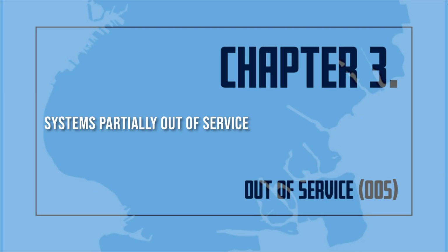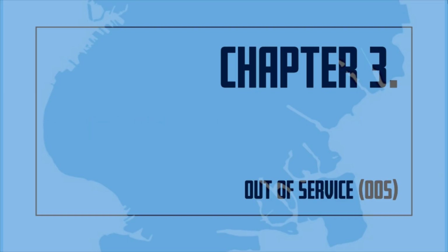The certificate of fitness holder and the impairment coordinator shall be made aware of and authorize the placement of systems out of service that are planned to be shut down. The impairment coordinator, prior to taking a system out of service, shall determine the duration the system is to be out of service, inspect the areas of the building affected and assess the increased risk, notify the insurance carrier, the central station operator, if so equipped, the occupants of the affected area, and place out-of-service tags and discs at the appropriate locations. Fire Code 901.7.4. Impaired equipment.